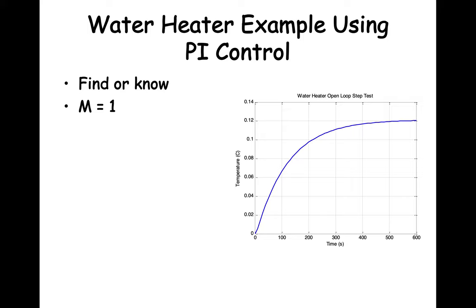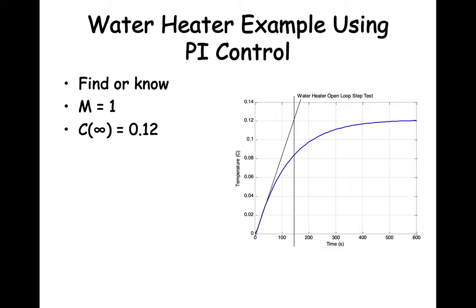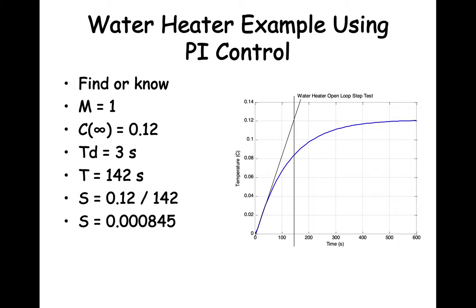From the graph, we see that C infinity is 0.12. Then we add the tangent line and the vertical line when the tangent line crosses C infinity. We can find that the apparent transport lag time Td is 3 seconds and the process time T is 142 seconds. Then knowing C infinity and the process time T, we can calculate the slope: 0.000845. Finally, we can calculate the process steady state gain K, which is 0.12. So now we know M, Td, and T.